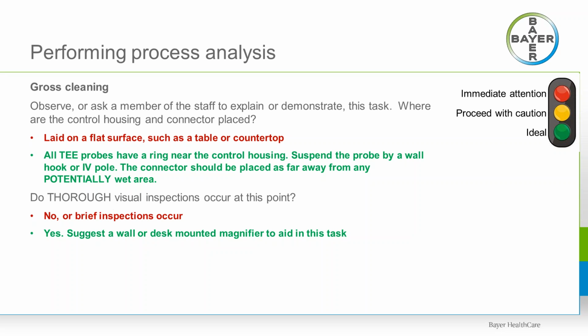Most TEE probes have a ring near the control housing, whether it's steel or plastic. This can be used to hang the probe from a wall-mounted eye hook. So you're protecting that control housing from accidental splashage. Again, this is an ideal time to perform a thorough visual inspection. It's the cleaning personnel that play the most critical role in this process. And most probe manufacturers stress this part of the process in bold text in their manuals.